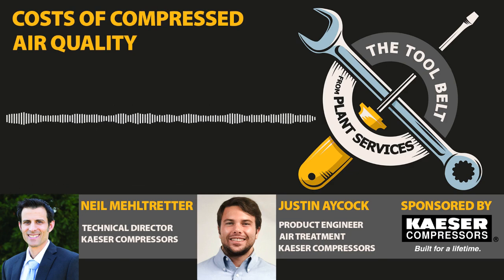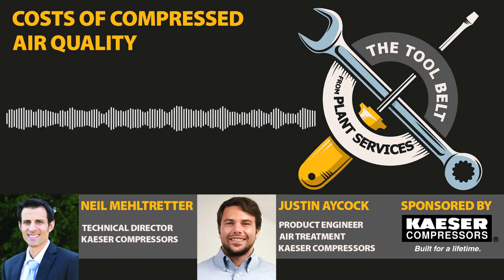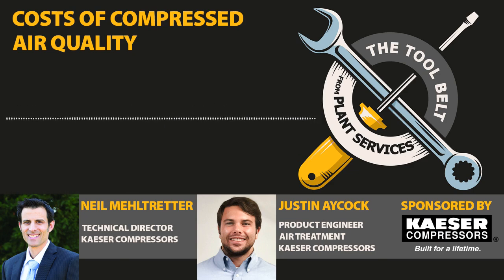But as Neil said before, whenever you turn up the pressure, you're going to increase the cost. The rule of thumb is for every 2 psi increase, it correlates to about a 1% increase in energy costs. So as Neil said earlier, you do need to have the pressure at the lowest possible amount just so you can save some money.